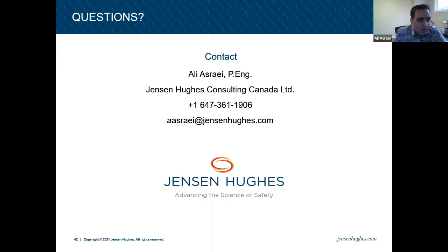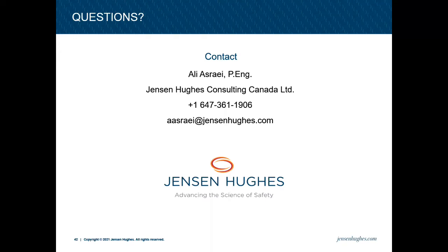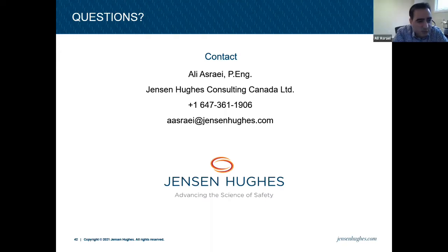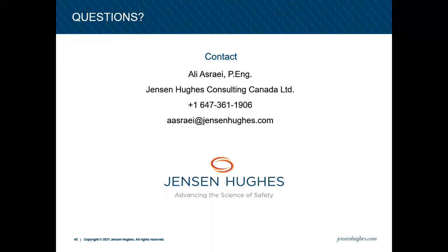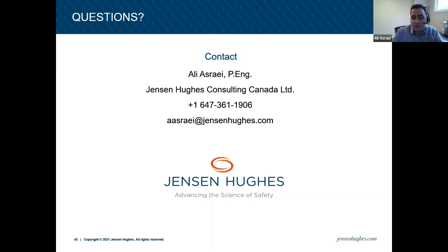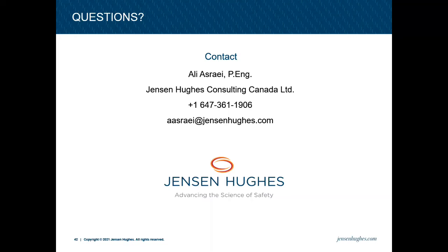The next one's going to be challenging for you to answer, I know. If an existing building has no previous test records, would you insist that an engineer be involved prior to anyone, contractor, fire department official, or fire alarm technician, testing the smoke control system? There are no previous test records. Would you insist an engineer be involved prior to anyone testing the smoke control systems? I don't know. Technically, that's what the fire code says, right? Well, it depends on if it's a measure or a system.